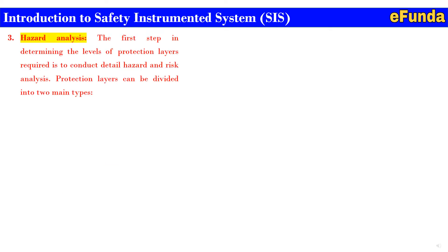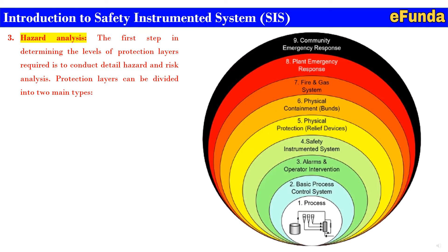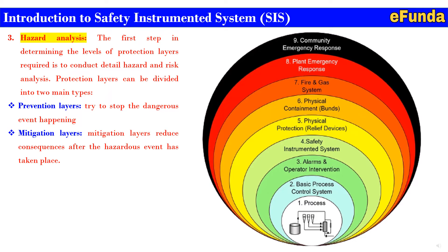The first step in determining the levels of protection layers required is to conduct a detailed hazard and risk analysis. Protection layers can be divided into two main types. As shown in the figure, the layers are: (1) process, (2) basic process control system, (3) alarm and operator intervention, (4) safety instrumented system, (5) physical protection — relief devices, (6) physical containment, (7) fire and gas system, (8) plant emergency response, and (9) community emergency response. The two types are: prevention layers, which try to stop the dangerous event from happening, and mitigation layers, which reduce the consequences after the hazardous event has taken place.